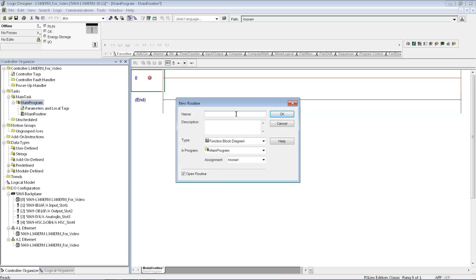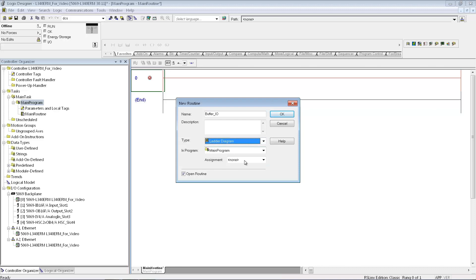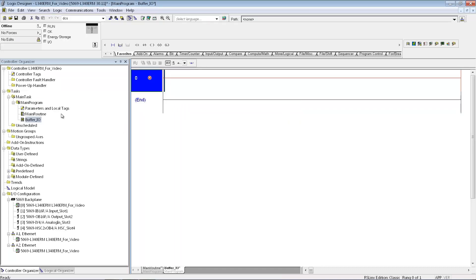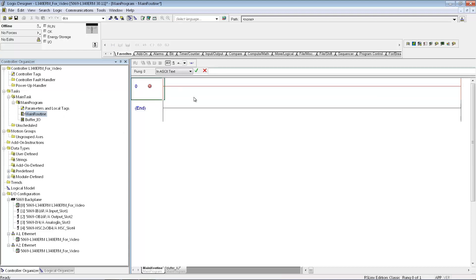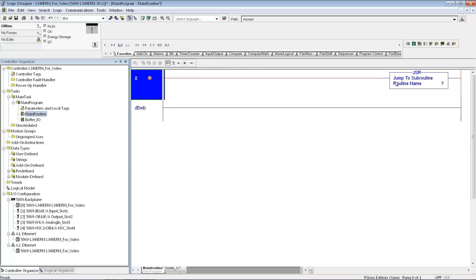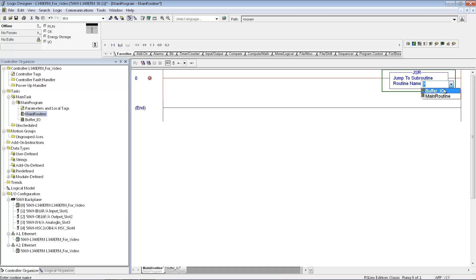So I'll just call this Buffer_IO, it's going to be a ladder program, say OK. Now I'll go back to my main routine, and the first thing I'm going to do is set up a jump to subroutine, and now I can select that subroutine. In this case, I'm just going to make a Buffer_IO module because ControlLogix, CompactLogix, they are asynchronous as far as the way they scan the I/O. So I'll set up a Buffer_IO subroutine so that then I will just reference the tags that I create within the Buffer_IO subroutine for the rest of my PLC programs.